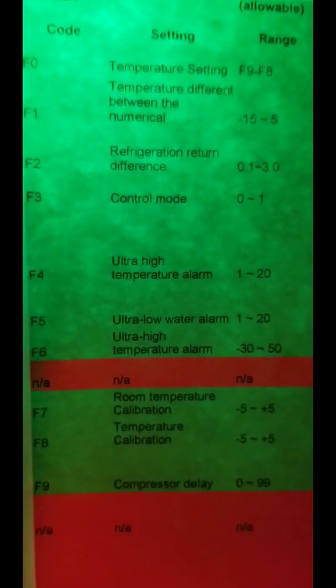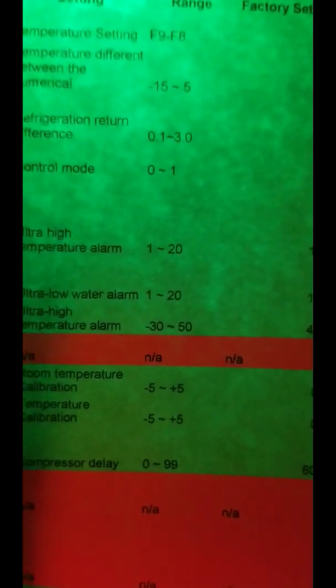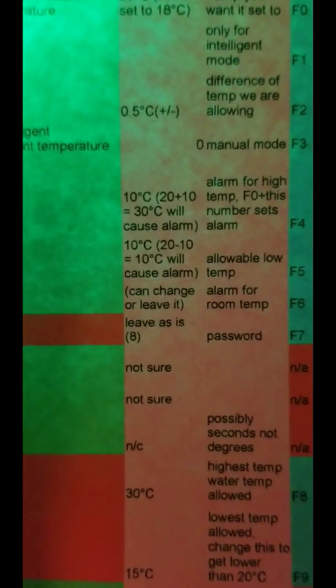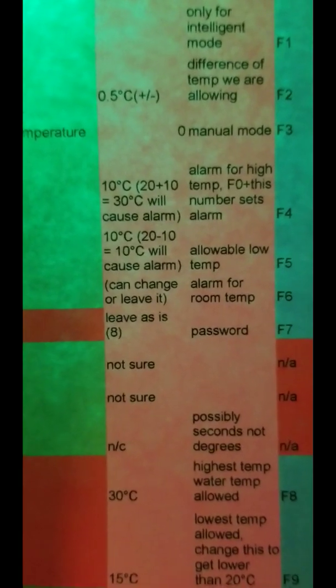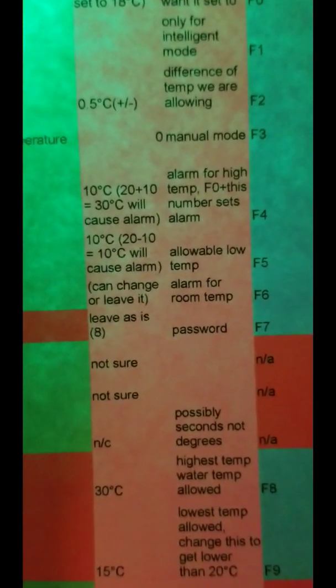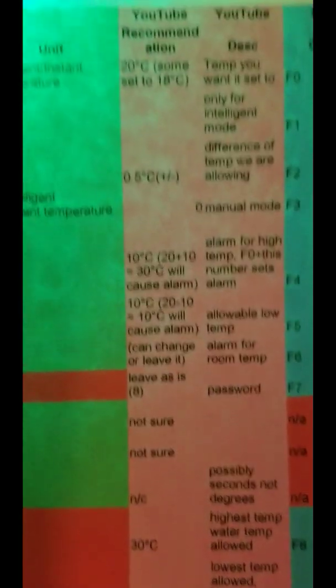The next one is F4, which is the ultra high temperature alarm, and F5 is the ultra low water temperature alarm. Right now they're at 17 and 16 degrees. Based on what I found for the S&A, F0 plus this number sets the high alarm, and F0 minus that number sets the low alarm. We want a 10 degree variance, so let's change those two. That's F4 and F5.